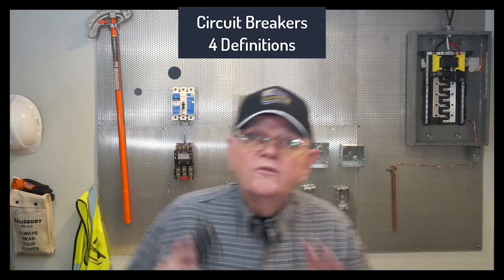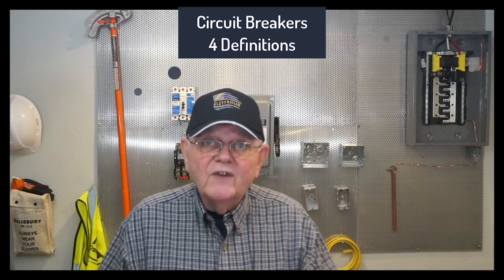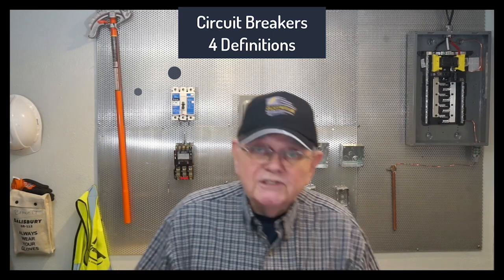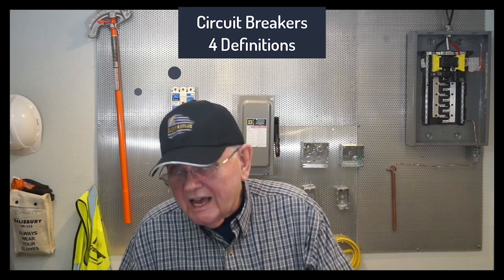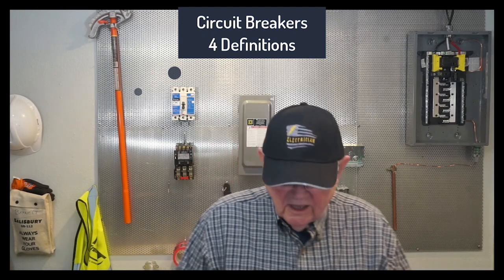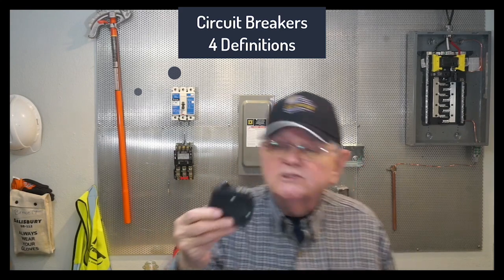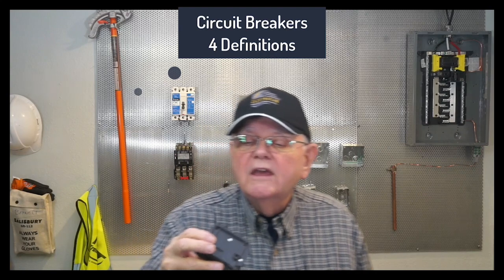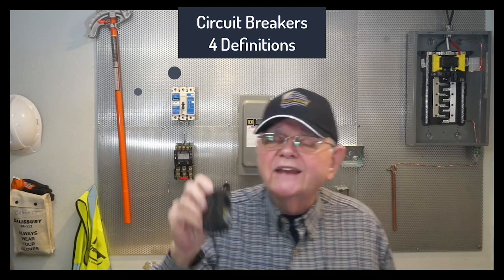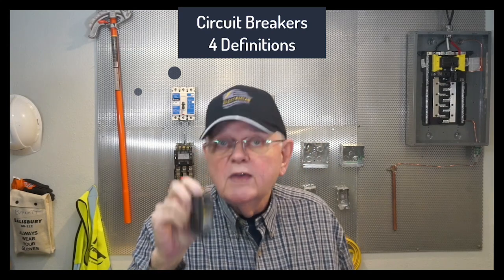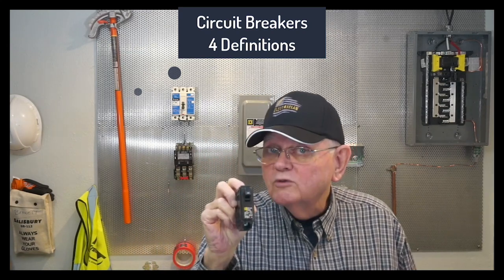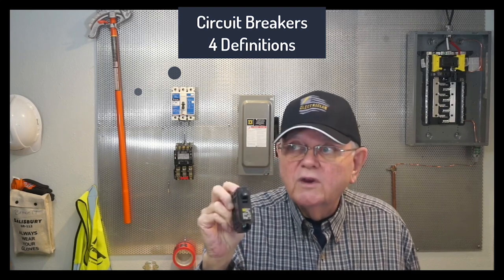Let's talk about circuit breakers a little bit, different types of circuit breakers. There are 4 different types of circuit breakers identified in the NEC. It talks about adjustable circuit breakers, instantaneous trip circuit breakers, inverse time over current breakers, and non-adjustable circuit breakers. So first of all, a standard 20 amp circuit breaker, molded case because it's all in molded plastic case, right? And I take a look at this, and it is called an inverse time circuit breaker, meaning that the more current that flows, the faster it trips, which is what I want.